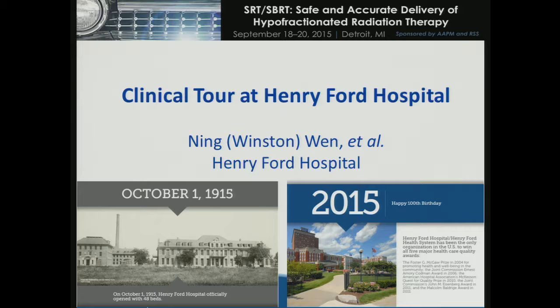That's an excellent point, and especially at 1 by 1 or things less than 1 by 1. We have encountered this issue in the clinic. You can't reconcile the output factor differences between film, like if you do GAFchromic film, and even diode. There's about a 5 to 7% difference, and that's exactly because of those perturbation factors that the gentleman referred to. And this is where the task group protocol is going to help us, hoping.